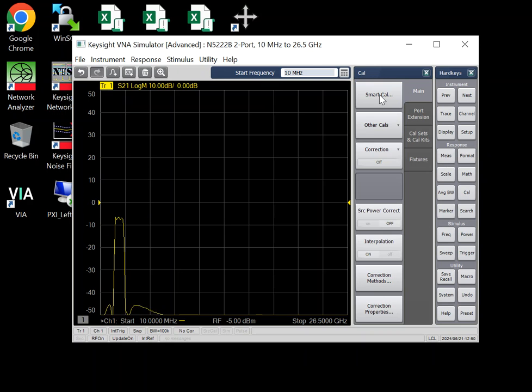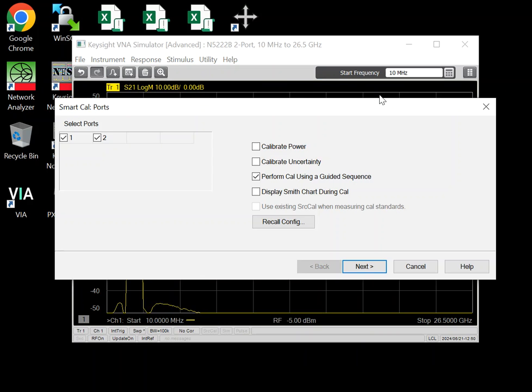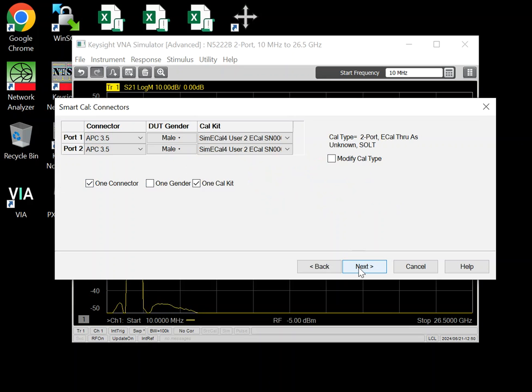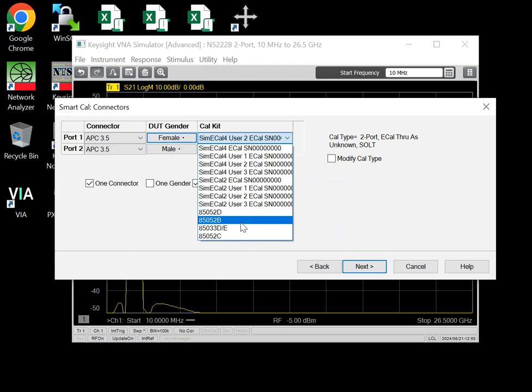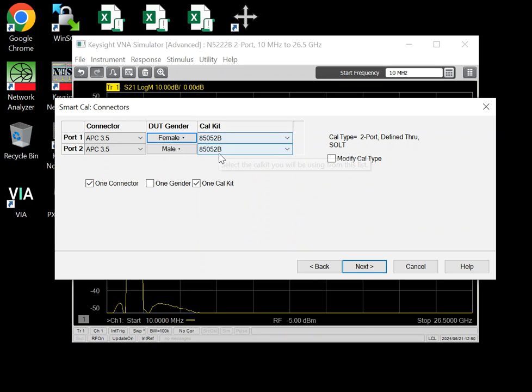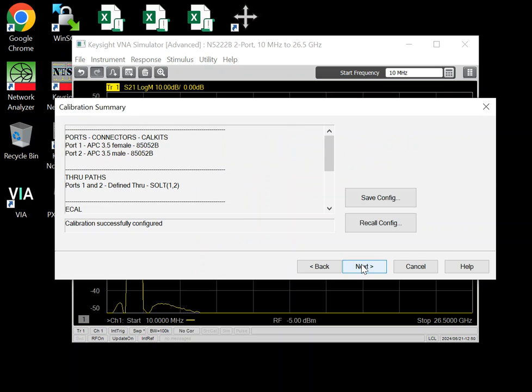Then you go to Cal, SmartCal. It by default picks ports 1 and 2. You leave everything as default. Let's say the DUT is female, male. We will pick the 85052B. And here it says two port count. It defaults to two port Cal.